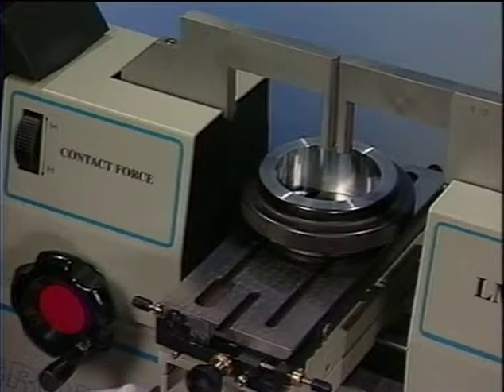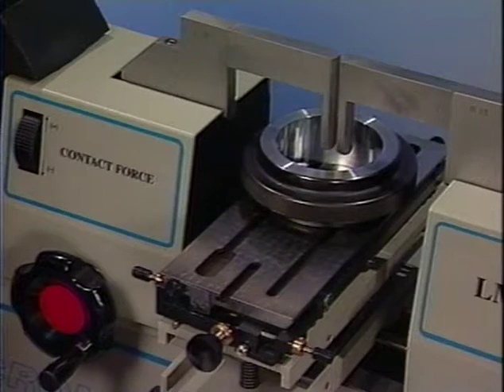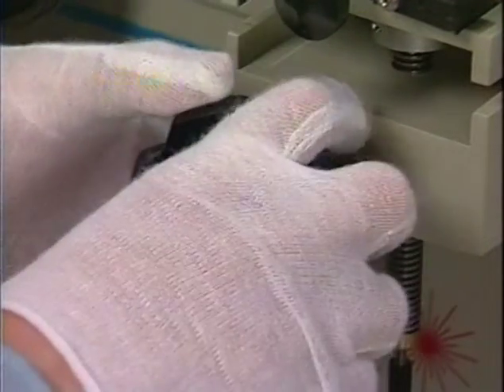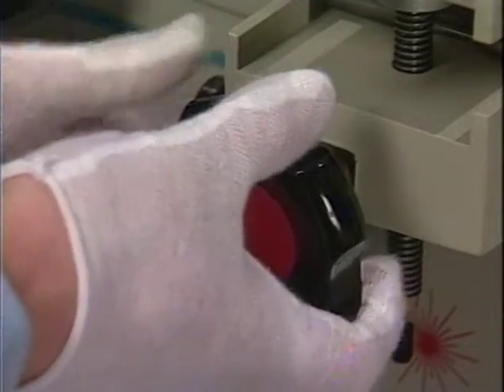To calibrate a ring gauge, select the ring gauge icon in GageCal and place the probes within it. The ring is quickly positioned by adjusting the table. Once positioned, you can move the table up and down to measure the bottom, middle, and top of the ring.